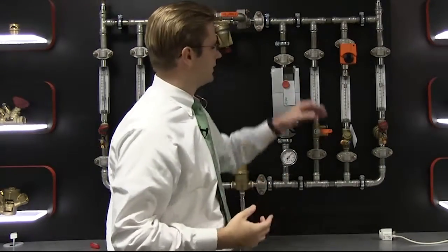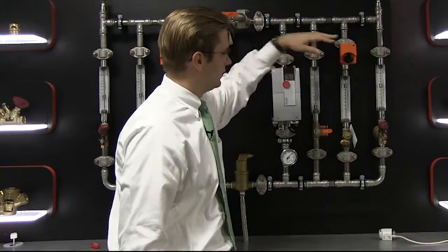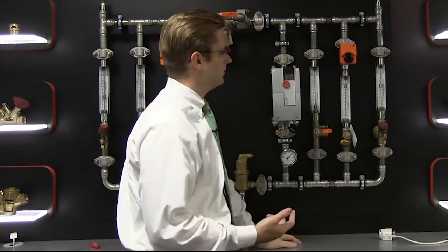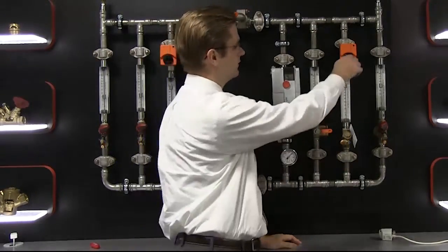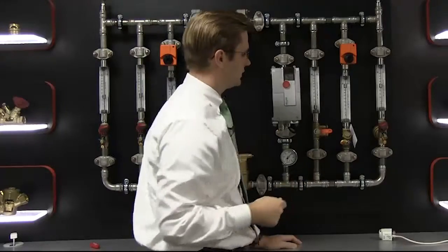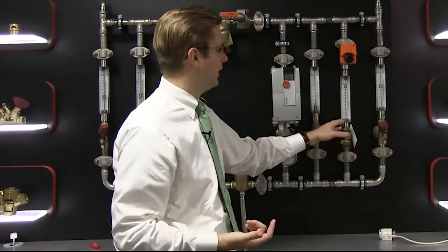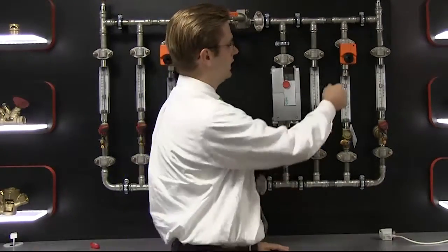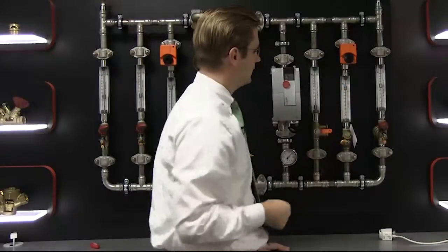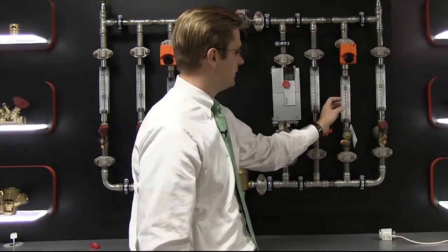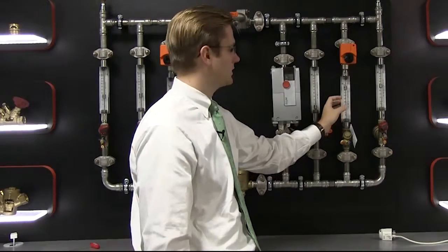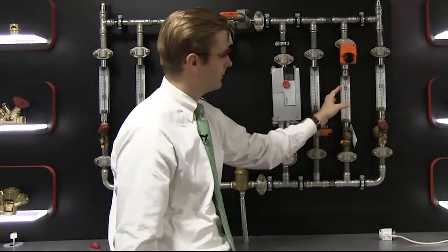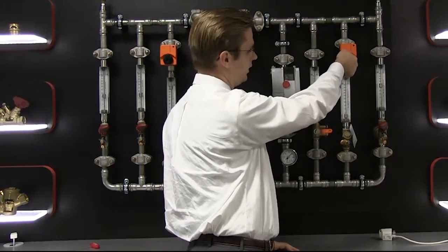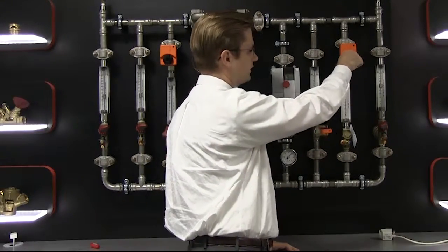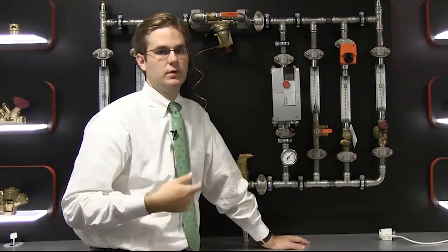The one issue, though, is with a modulating control valve. When the modulating control valve wants to close down to 3/4 closed, as the control valve closes down, the automatic valve opens up and overflows the control valve. Even when I get to 50% flow, you can see that this flow rate should be down at 2.5 GPM, but it's still up well above 4.5 GPM. Eventually the control valve will gain authority, but what you've done is you've turned a modulating control valve into an on-off control valve.